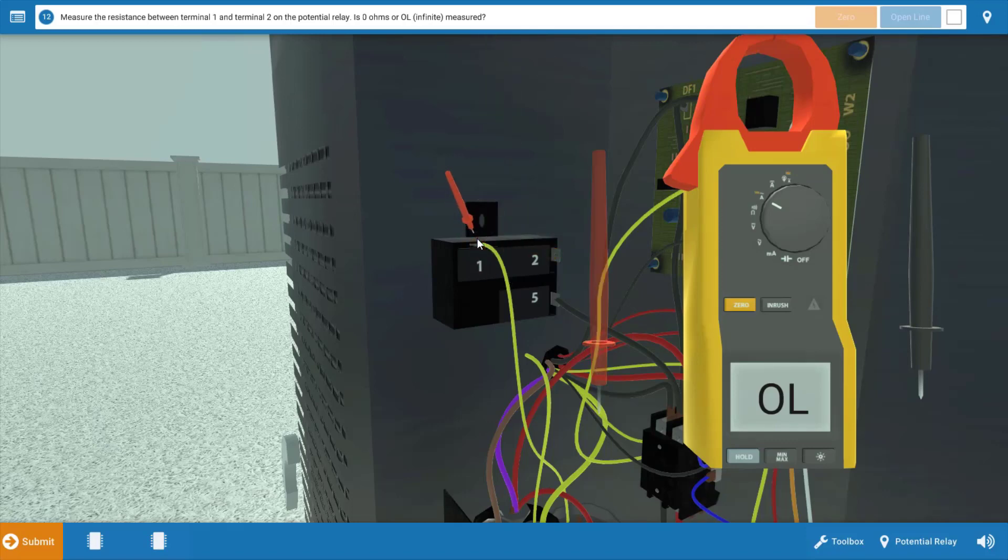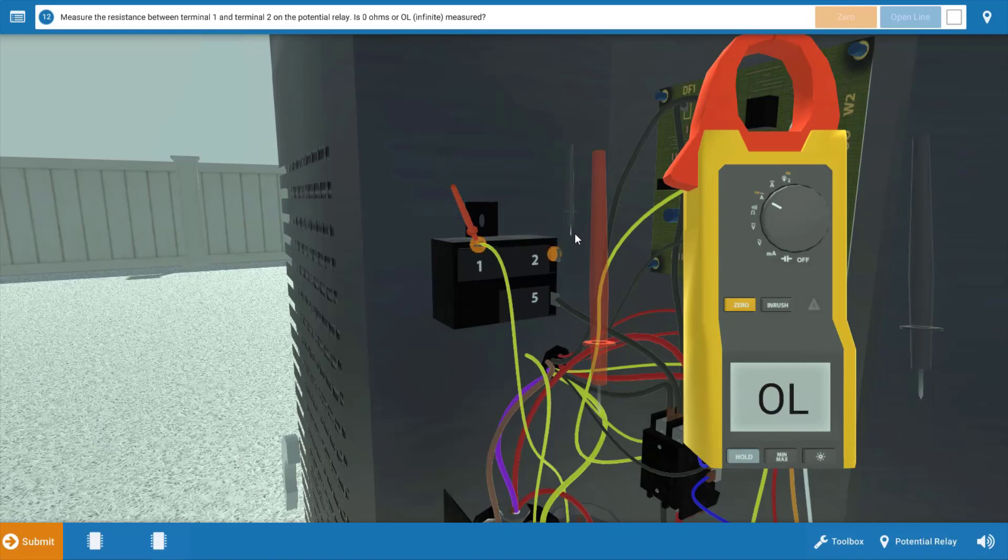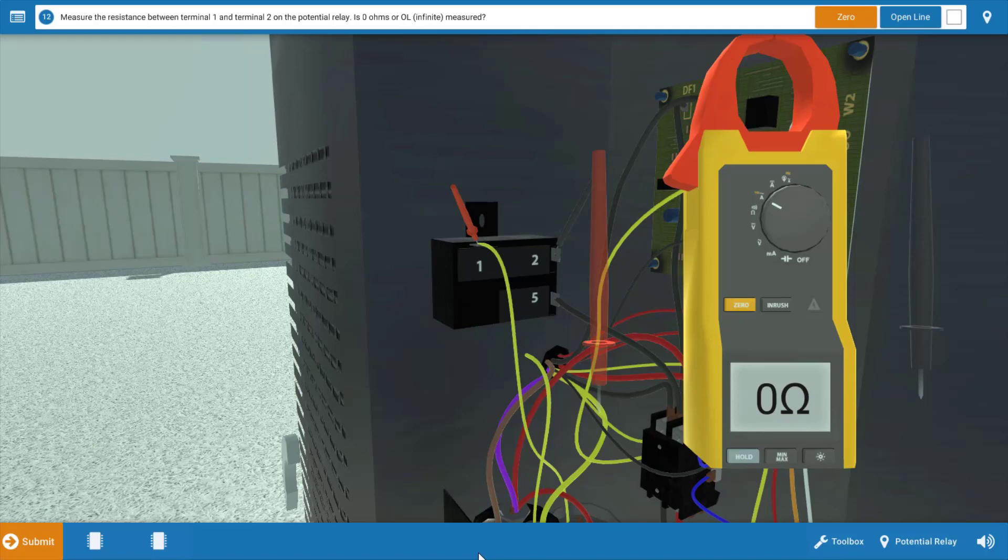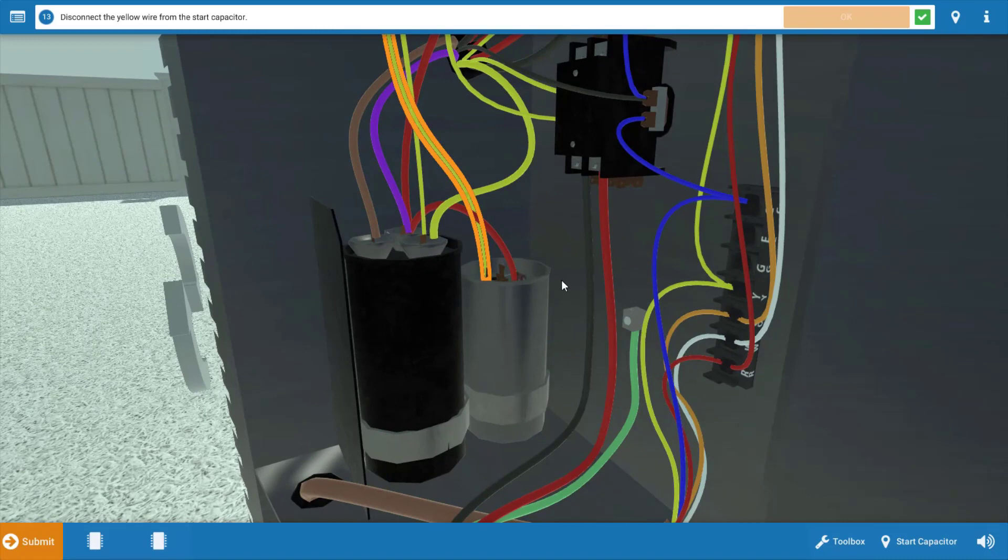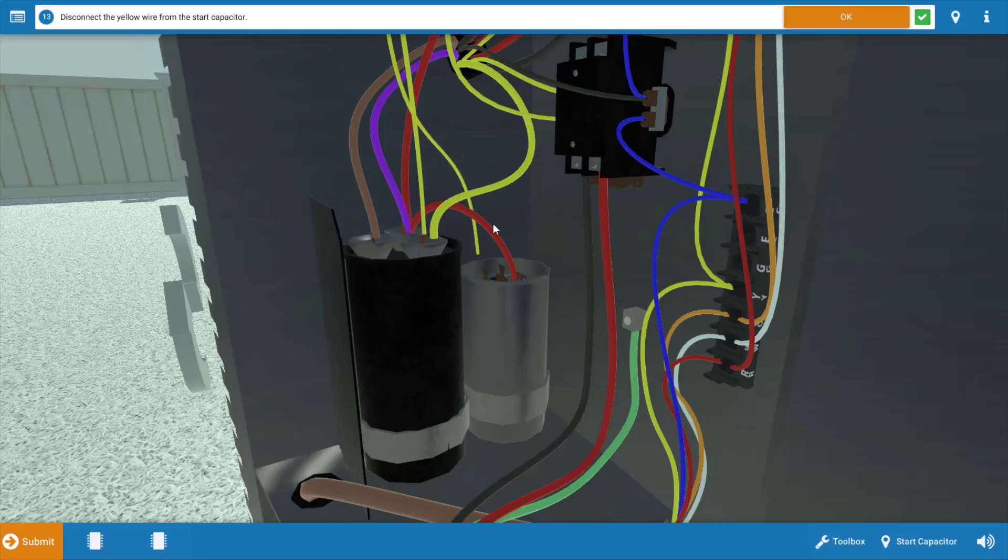So we're going to start by placing the leads across terminals one and two to verify the position of those contacts. And we do, in fact, have zero ohms. So our potential relay checks out here. So click zero on the procedure guide, and our next step is to proceed to the capacitors. We need to disconnect those or isolate them in order to measure capacitance value. So we're going to click on this wire right here to disconnect it from the capacitor. Click OK.